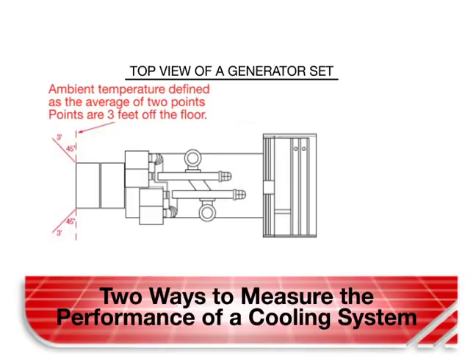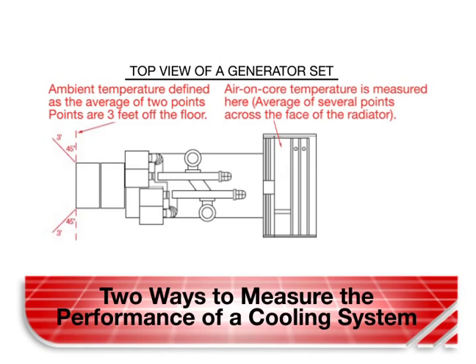The AOC temperature, on the other hand, is measured on the face of the radiator. The air flowing through the radiator is significantly warmer than the air entering the system. So AOC temperatures are higher than corresponding ambient ones.